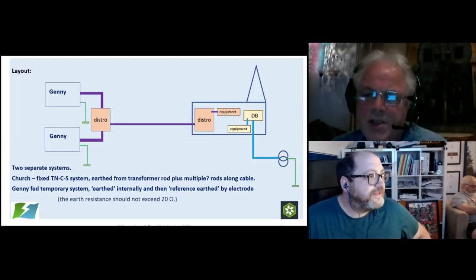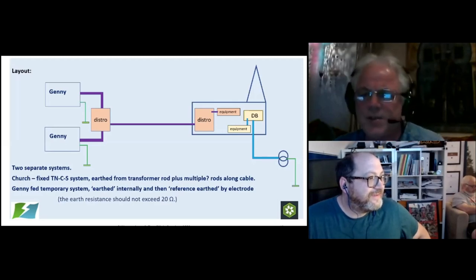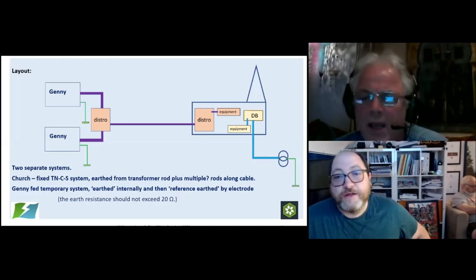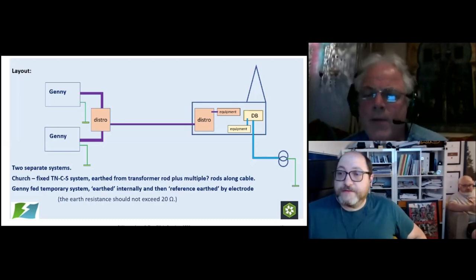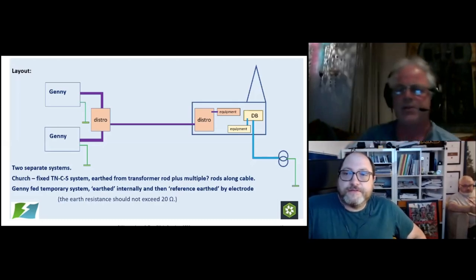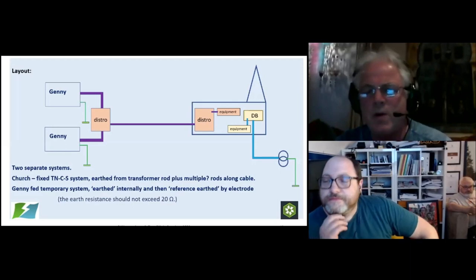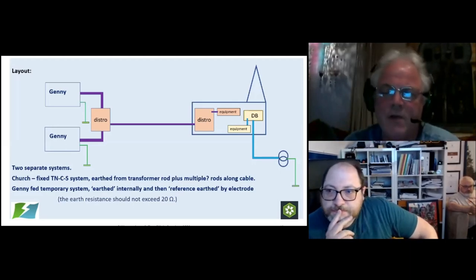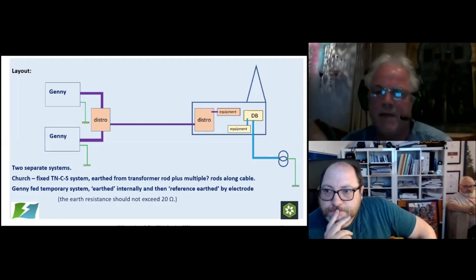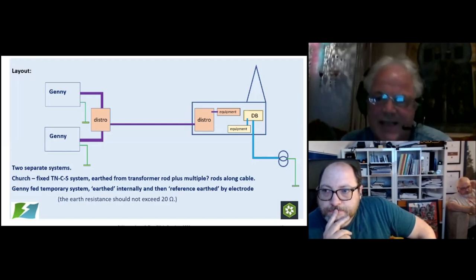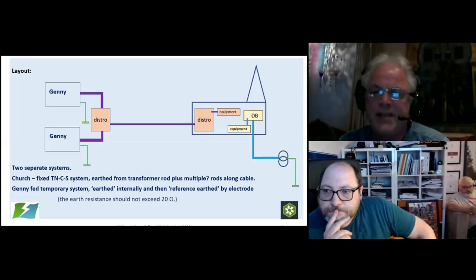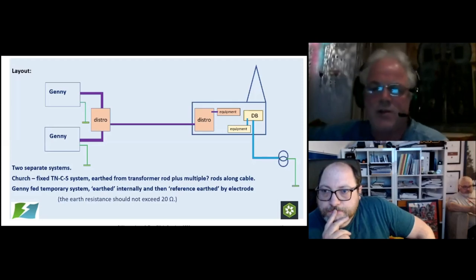And this is all we can legislate for, single faults. Okay. There was also a question about the earth resistance not exceeding 20 ohms on the earth electrode. People get confused about this because, when we're talking about an earth electrode on a generator, remember, you can't test that. Unlike an earth electrode on a fixed installation, which you can test with an earth loop impedance tester, because you're testing the earthing through the ground back to the transformer.